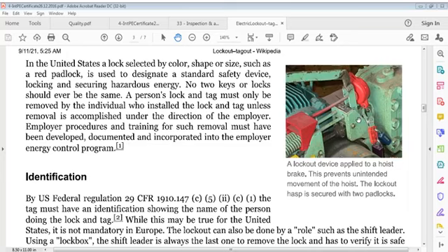Okay. It says the lockout device is applied to a hoist brake. This prevents unintended movement of the hoist. The lockout is secured with two padlocks. Now, in the US, a lock selected by color, shape or size, such as a red padlock, is used to designate a standard safety device, locking and securing hazardous energy.